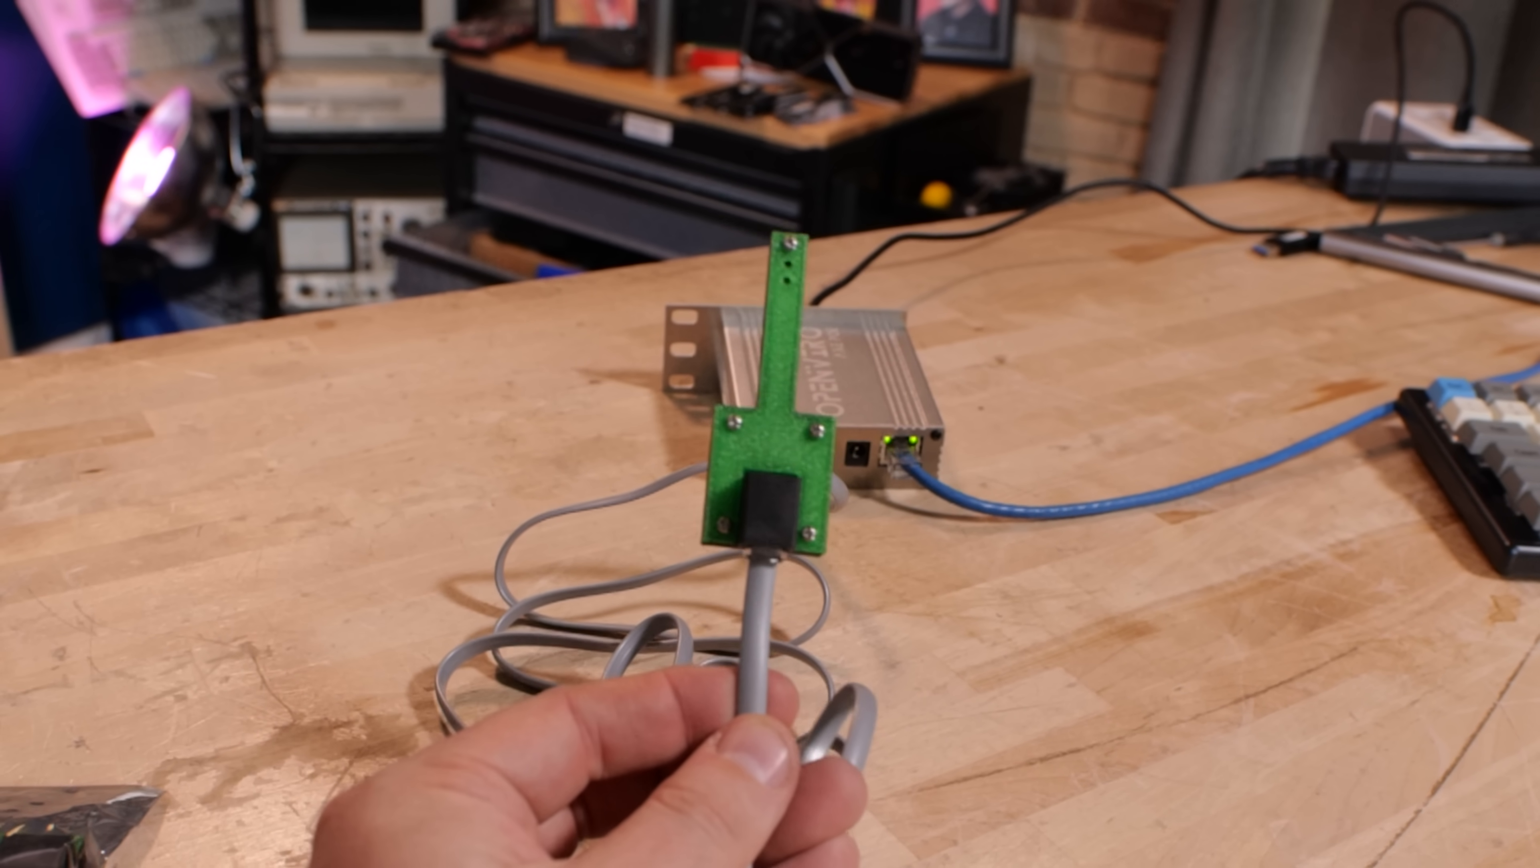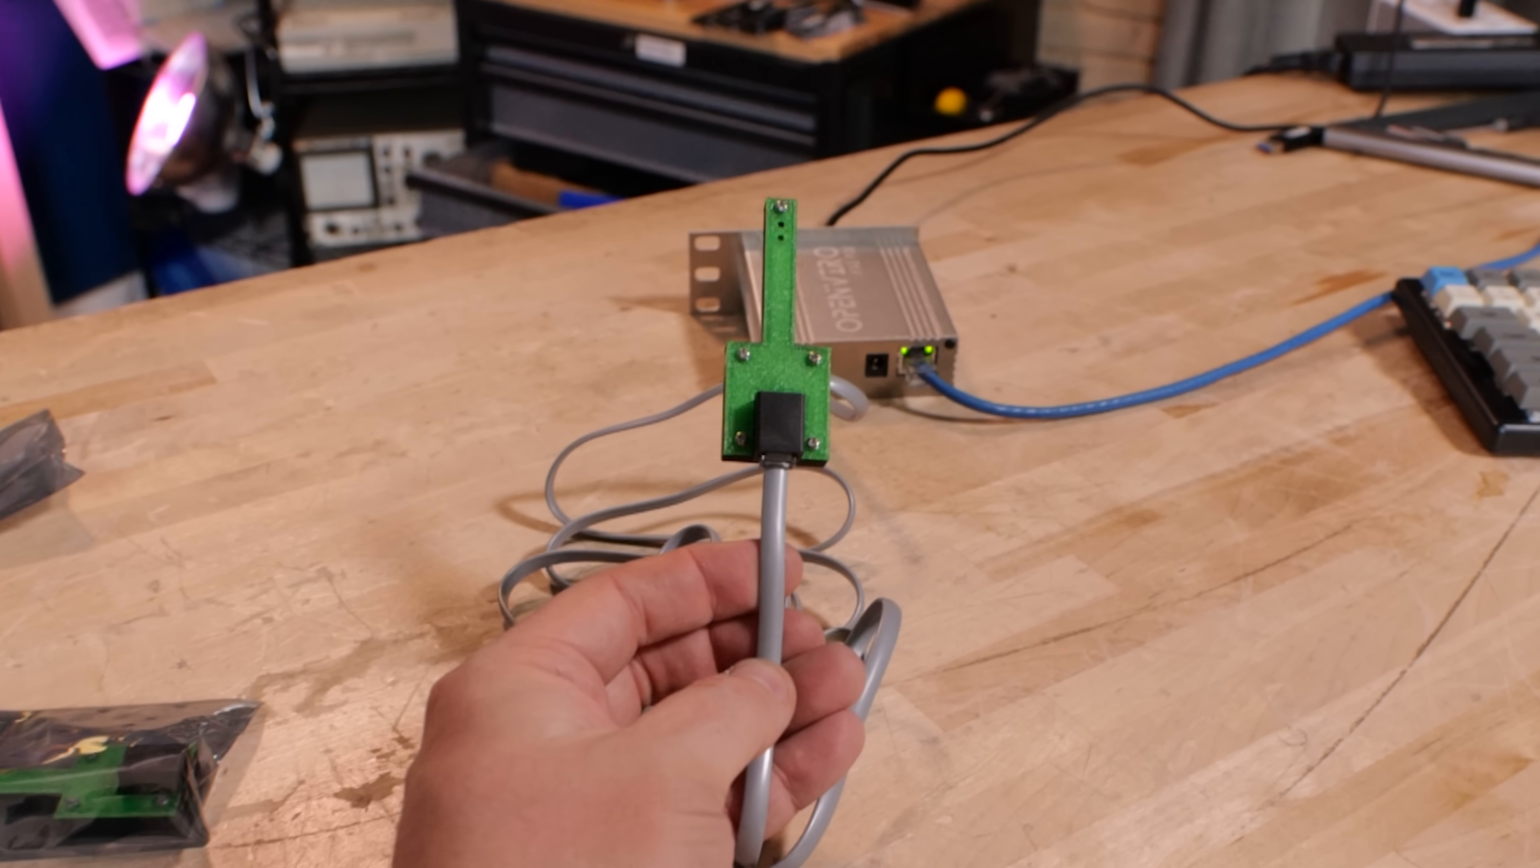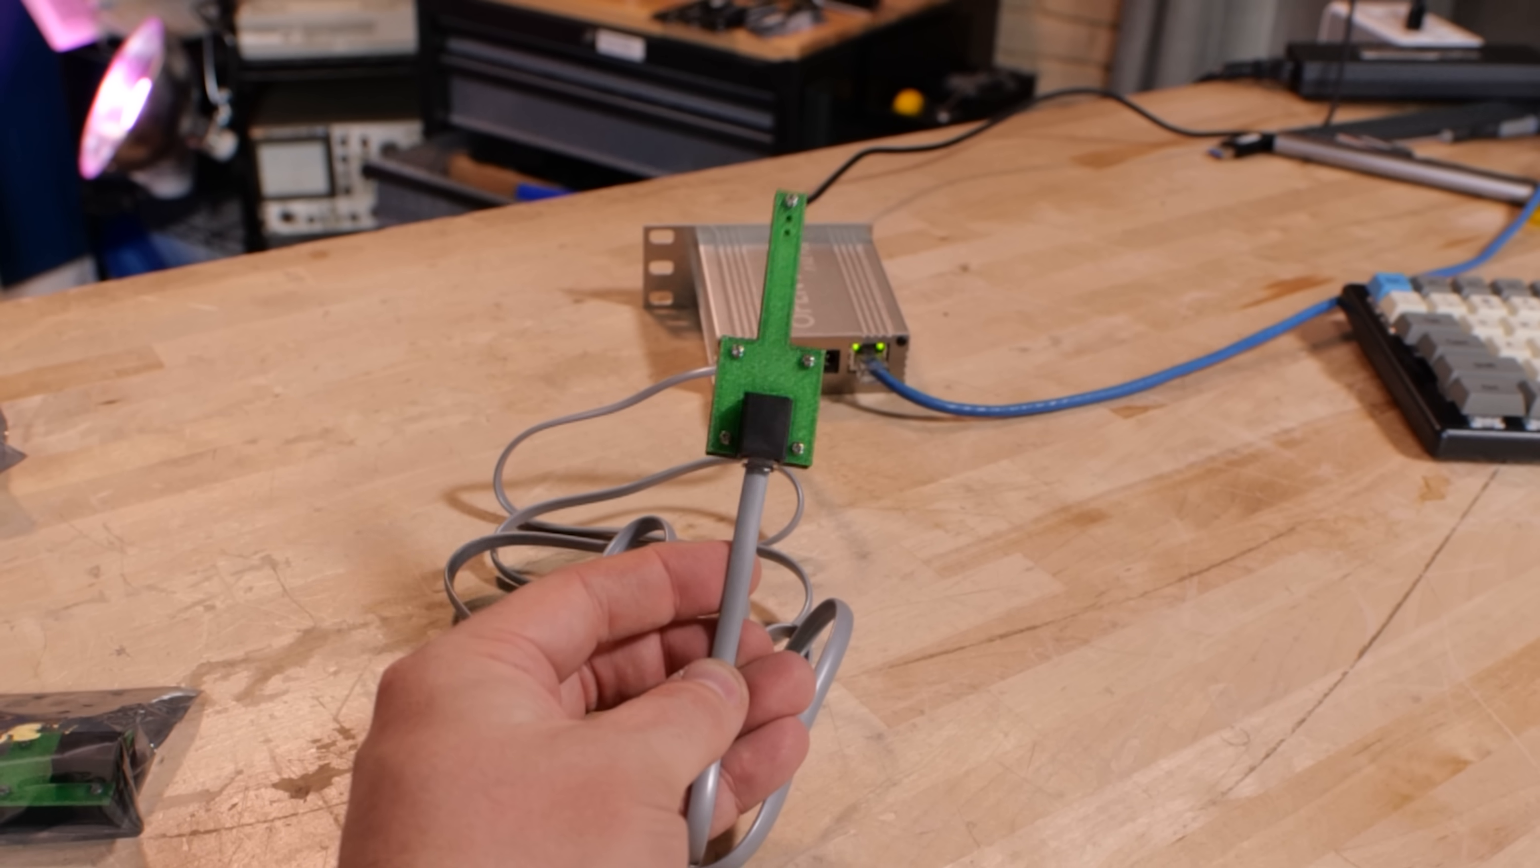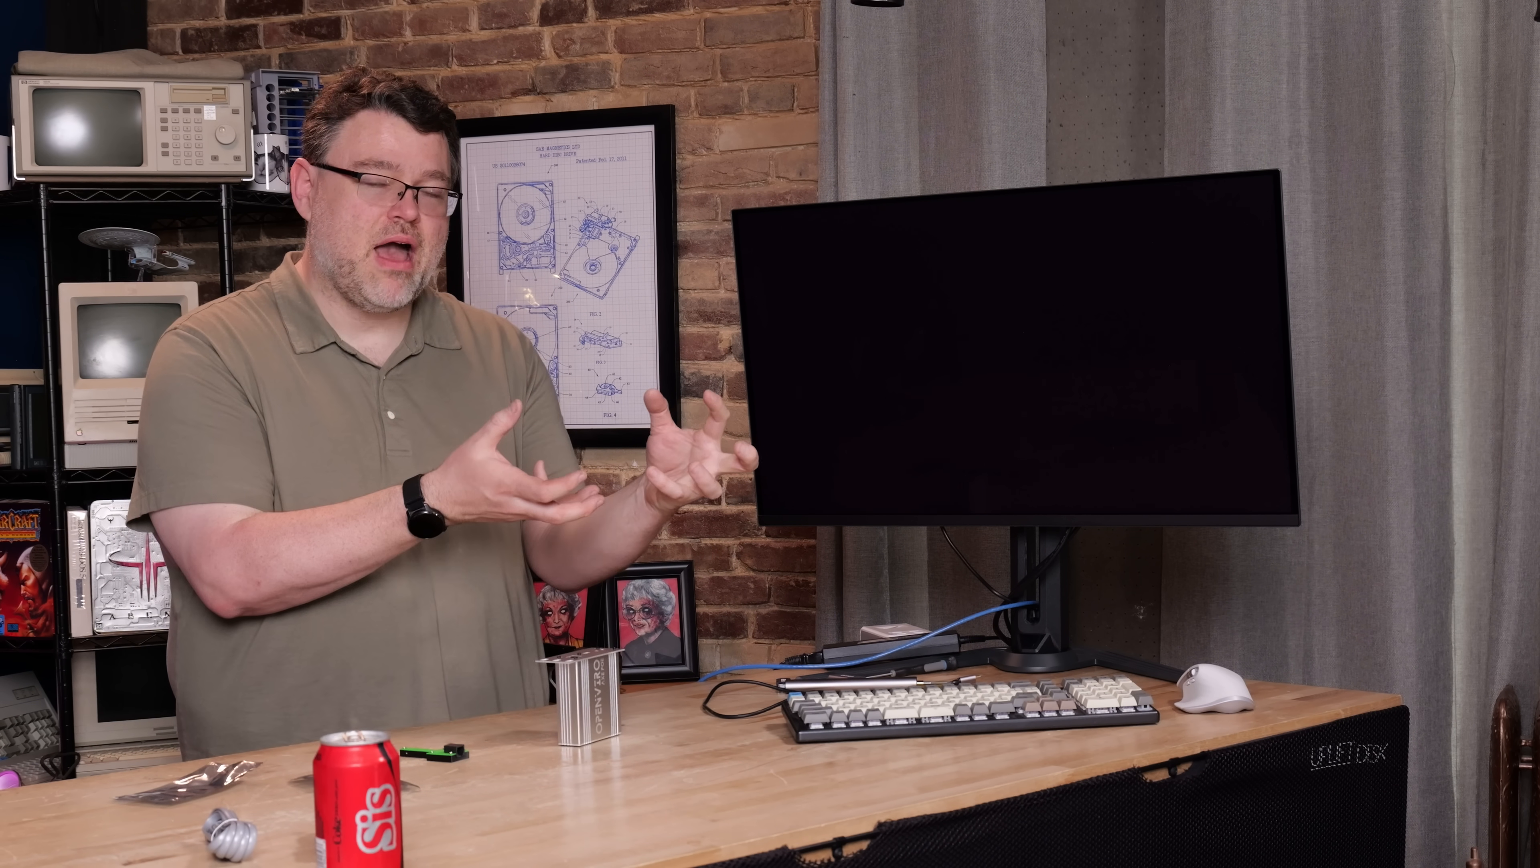The THP probes are based on the Bosch BME280 temperature, humidity, pressure sensor, and the operational range is minus 40 to plus 85°C, 100% relative humidity, and 300 to 1100 HPA. The accuracy with these is a half a degree C, and the probe time is very fast. You can get multiple probes per second, which if you've used any of the other built-in temperature sensors in backup power systems or power bar distribution systems, you're lucky to get one second probes. It's annoying and silly.